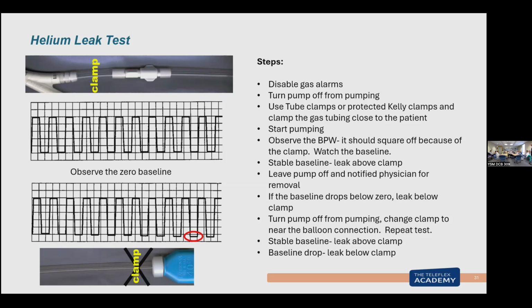It's very helpful. I usually think about doing this when we're getting the possible helium loss 2 alarms every 2 to 3 minutes. I don't see blood in the tubing, but the pump sees a problem. It sees a hole. It's not getting the helium back.